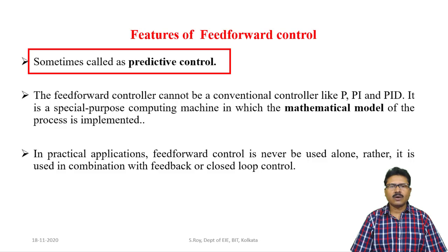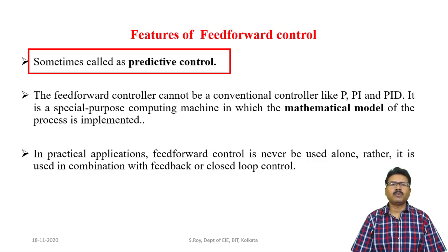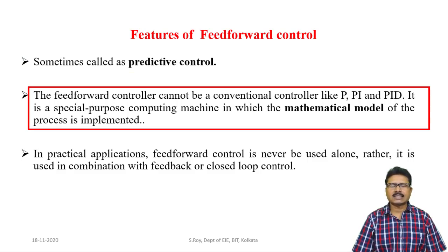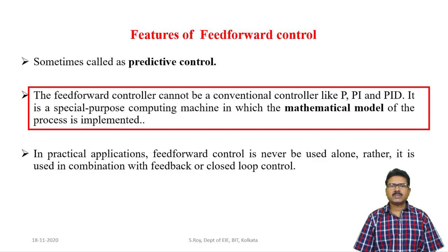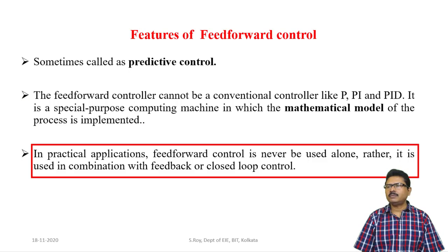Feedforward control is sometimes called a predictive control system because it predicts the control variable instead of measuring it. A feedforward mathematical model, based on the process characteristics, predicts what the output might be due to different load variables. Unlike conventional controllers like PID, feedforward control is a special-purpose computing system with a mathematical model of the process implemented within it. In practice, feedforward control is never used alone — it is used in combination with feedback or closed-loop control.